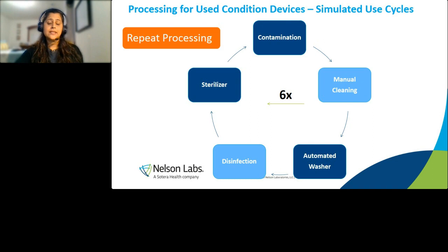So FDA implemented this in 2015 in their guidance document and specified you should consider simulated use cycling before you do a cleaning validation. And when that happened, it changed the whole realm of validations. And we had to do these cyclings where the healthcare facility would see a device processed from use to cleaning to disinfection, if that's the last phase, or sterilization. And we do that 6 times to make them into used condition. And then on the 7th time is when the validation would happen. So this was implemented just a few years ago to assess cleanability.